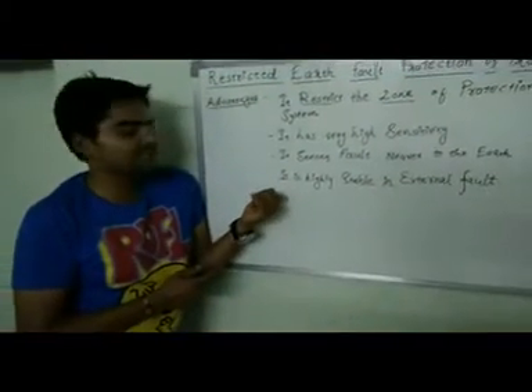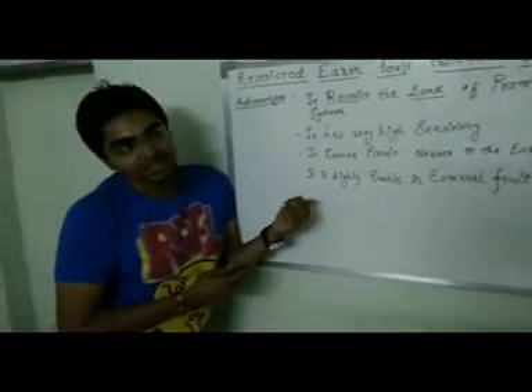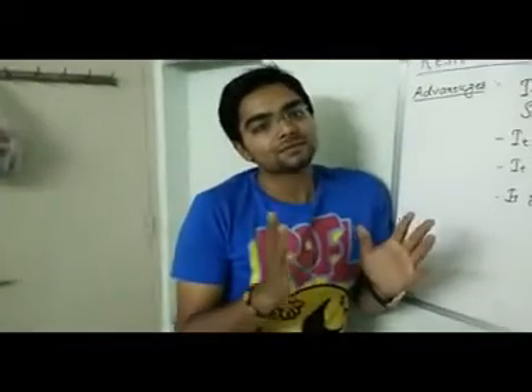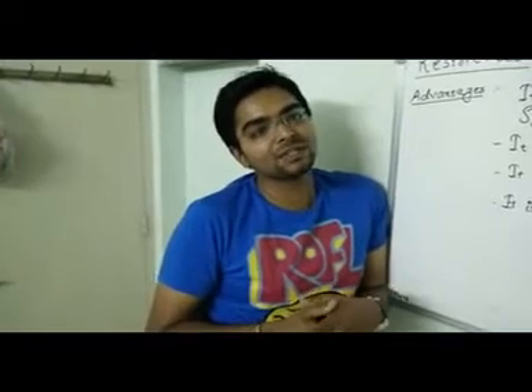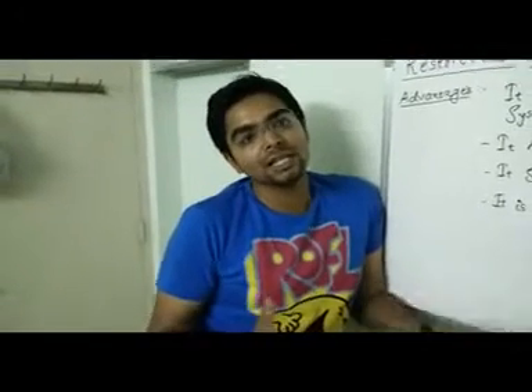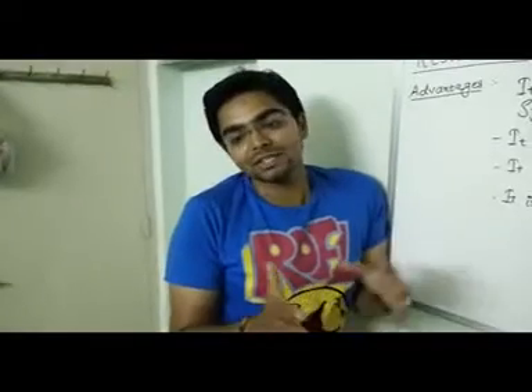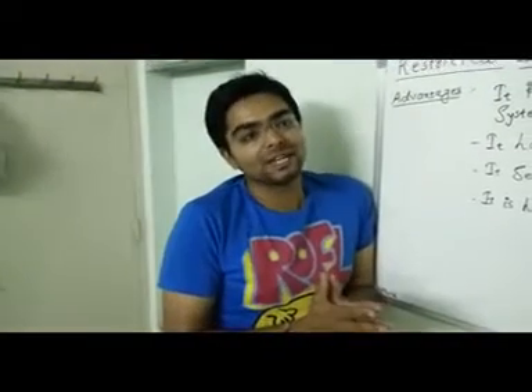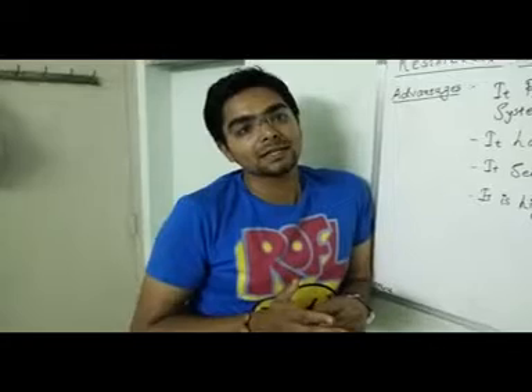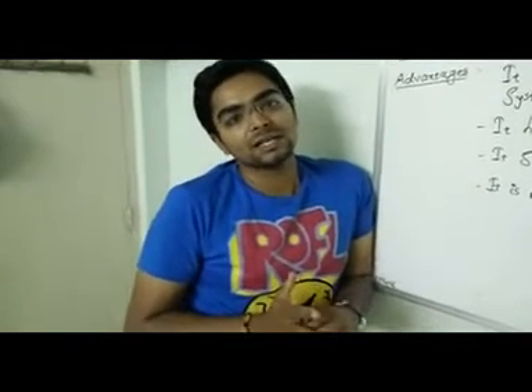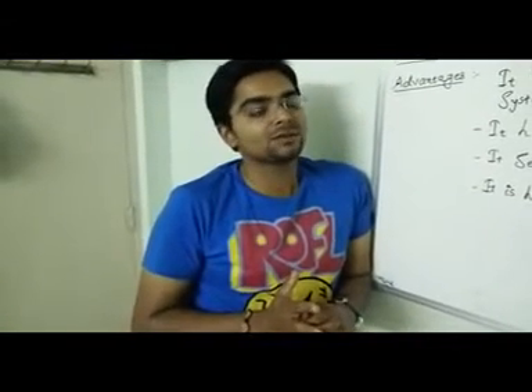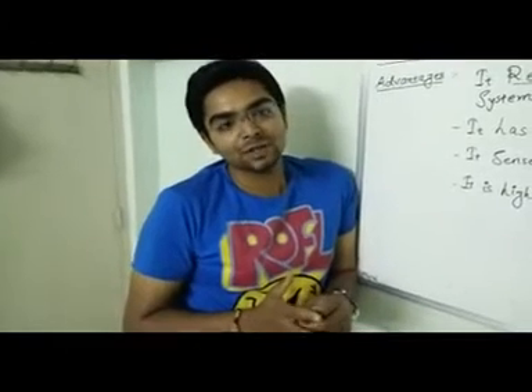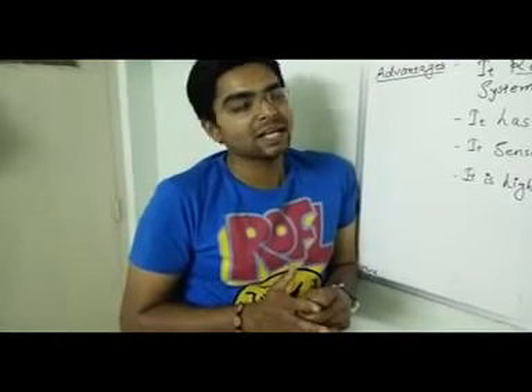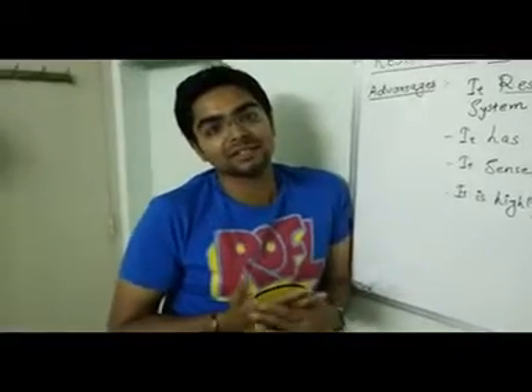And the last point, which is one of the most important points, is that it is highly stable in external fault. So if there is an external fault, it won't affect the internal protection system at all, and it won't harm the protection system. In the next video I will show the real simulation of the same thing, and we'll prove all these points and have a look at it.